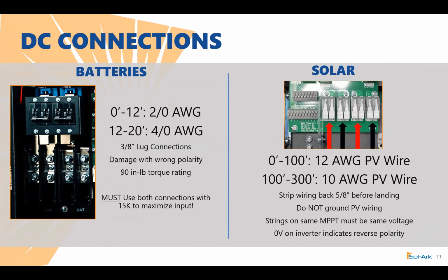Going further on the DC connections, we're going to talk a little bit about the battery terminals. On the left-hand side, that's a battery terminal from the Sol-Ark 15K. That's all going to be in that same user wiring area that we talked about. You can use 2/0 AWG wire for your battery terminals, and you can actually parallel it at the battery terminal as well, between 0 and 12 feet. And if you have some distance, 12 to 20 feet, we recommend using 4/0 AWG.